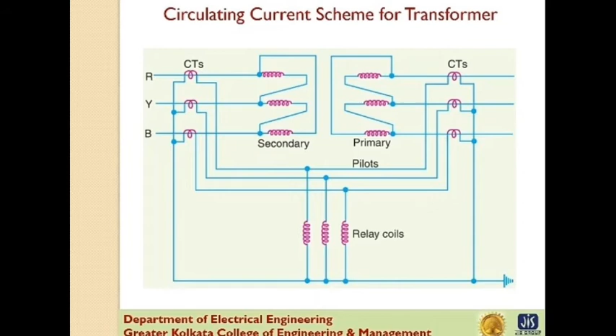When the power transformer is connected as star with neutral earth, in that case the current transformer is connected as delta, and when the power transformer is connected as delta star with neutral earth, the current transformer is connected as star delta. Thus, referring to this table, for a delta star power transformer, the CTs on the delta side must be connected in star and those on the star side in delta.